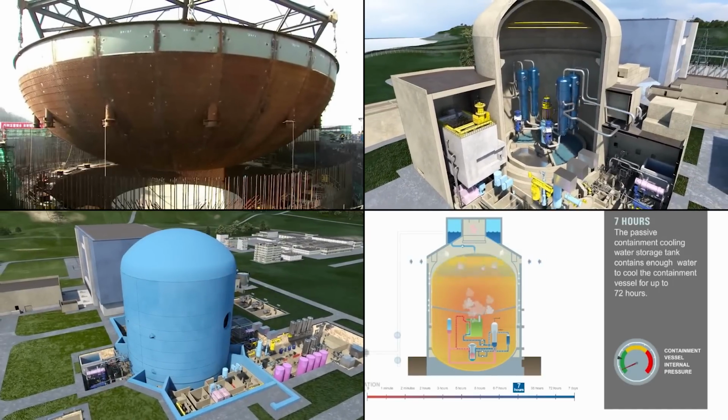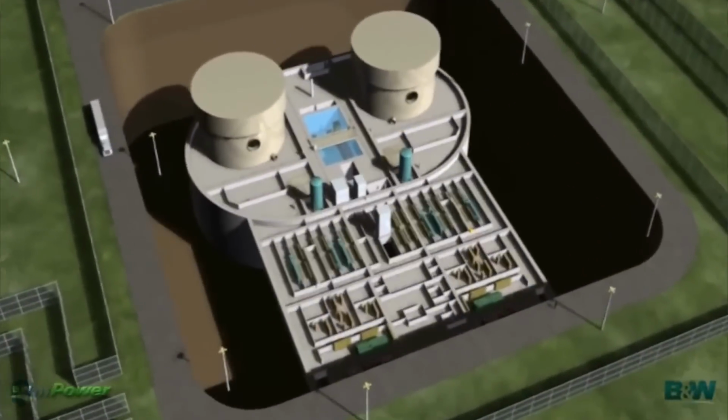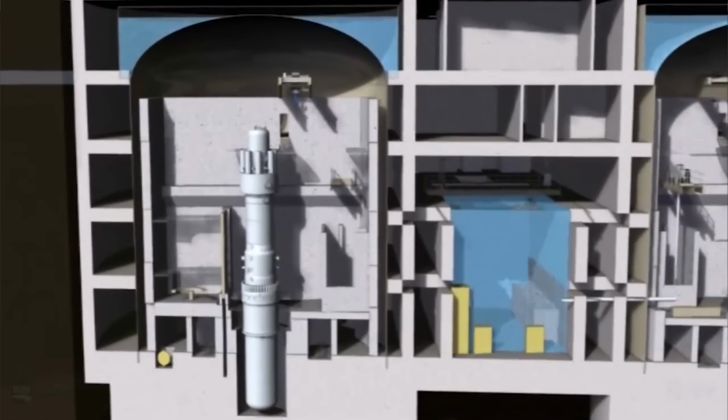Pressurized water reactor has to take 2,000 psi, which is a really thick pipe. It's typically 4 to 8 inches depending on the diameter of the pipe. We're doing new things with light water. The core, the pumps, the control rod drive mechanisms, the steam generators, the pressurizer, all in one steel pressure vessel. No piping penetrations in excess of about 3 inches in diameter. I'm working on that exact reactor.